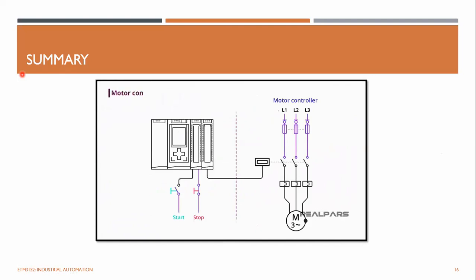Many types of motor controllers are available, and the various types and styles all have specific uses in industrial control. All motor controllers are designed to keep the motor from being energized until the controller is told to activate. Once activated, current can pass to the motor, which energizes the motor windings and starts motor rotation. Activation of the motor controller is typically accomplished with an electromechanical device built into the controller, also known as a contactor. Other methods can also be used.